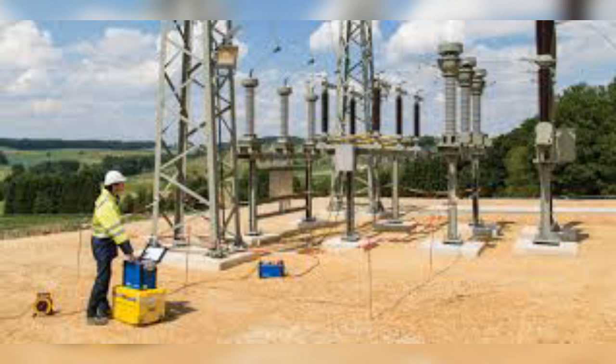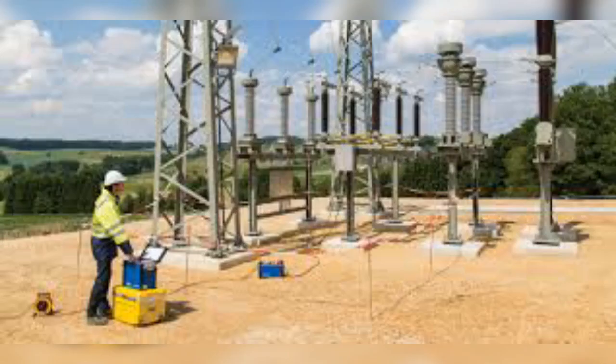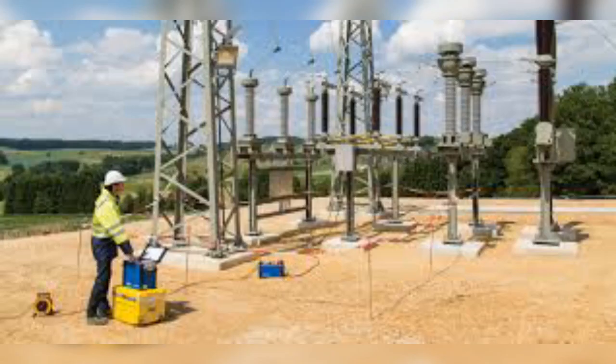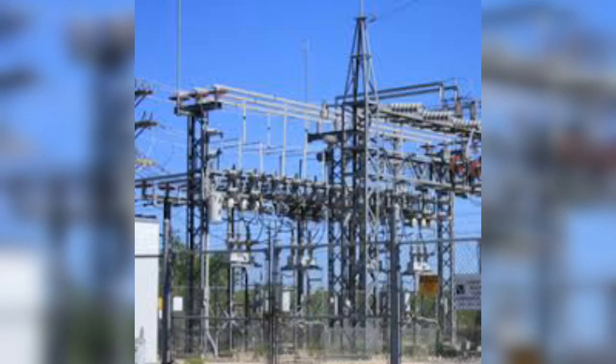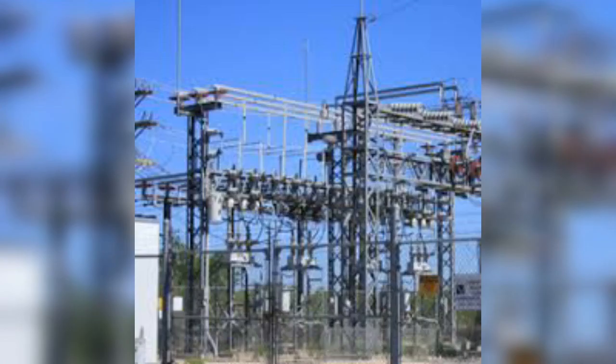Current transformers, DC supplies, circuit breakers and relays are some of the key components that protect and control the system. The reliability of the protection system depends largely on the performance of these devices. Failure of these components may leave the power system vulnerable, with the possibility of irreparable damage, and periodic testing ensures the protection circuit will operate when called upon.